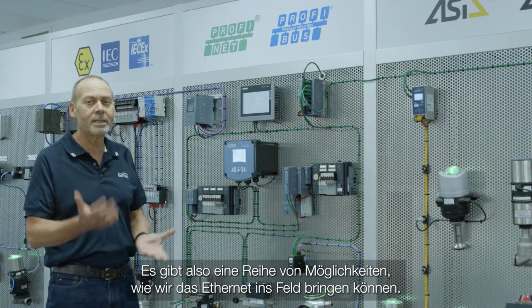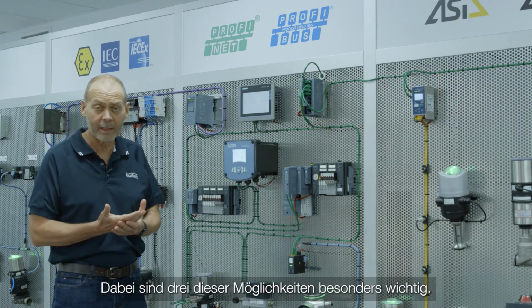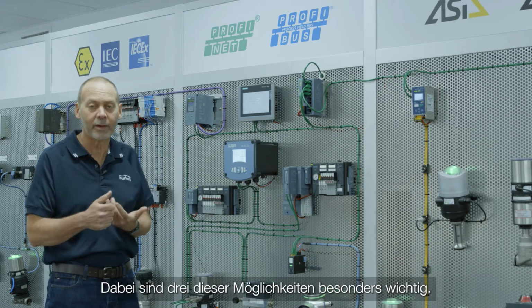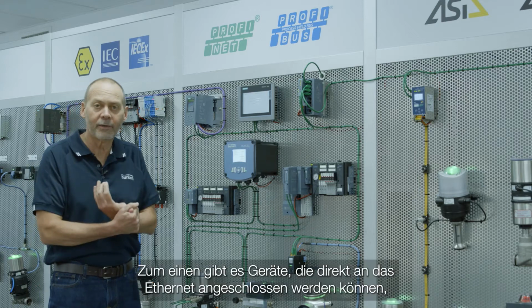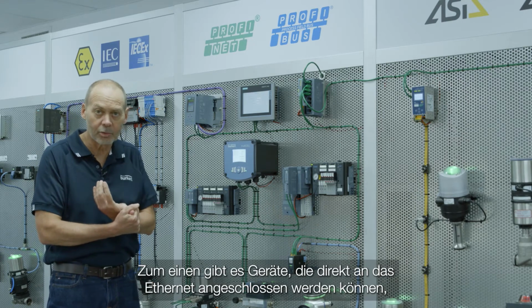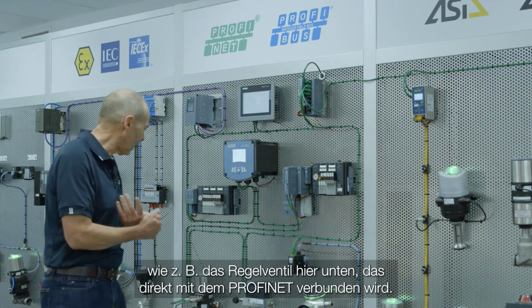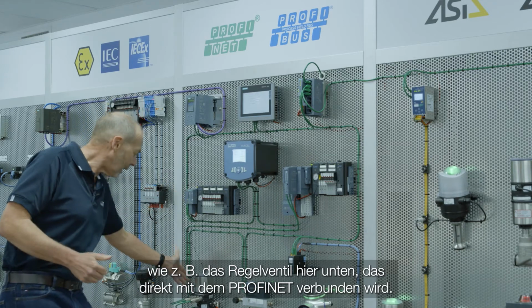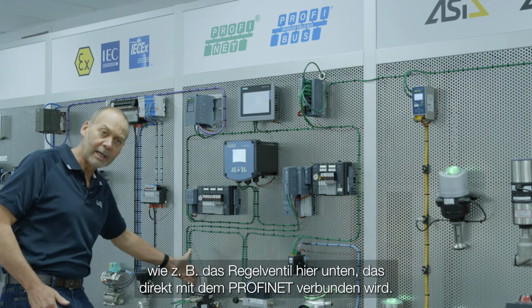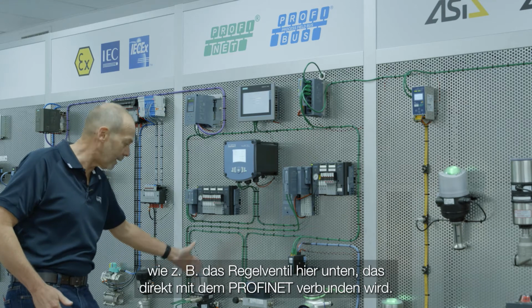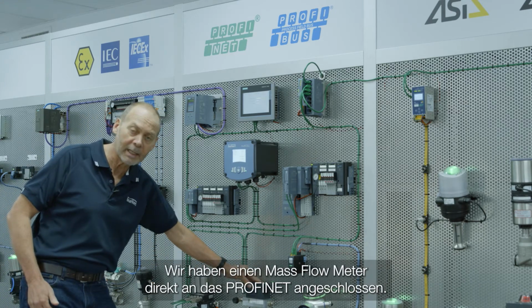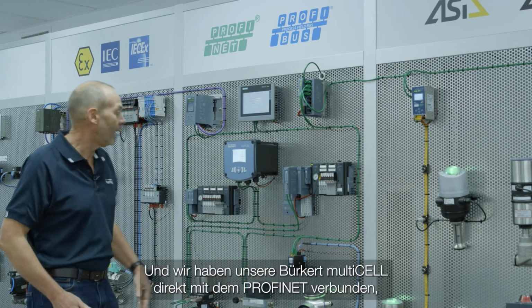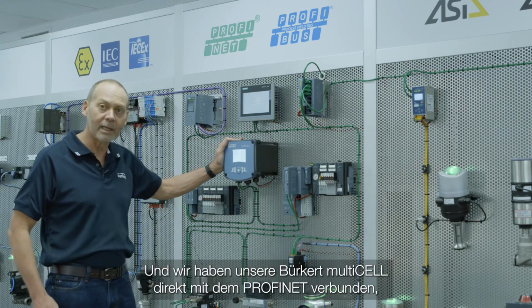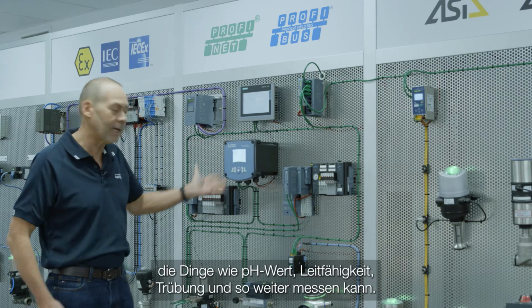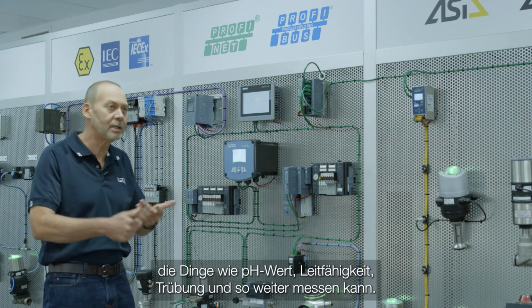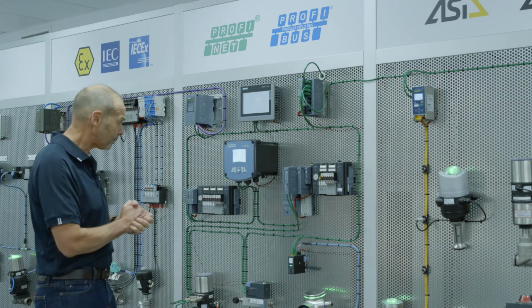So there are a number of ways that we can take Ethernet to the field, and there's three main ways you really have to consider. One is having devices that connect directly to Ethernet. As an example here, we've got a modulating control valve connected directly to the PROFINET. We've got a mass flow meter connected directly to the PROFINET, and we've got our Bürkert multi-cell connected directly to PROFINET, which may be taking in things like pH, conductivity, turbidity, etc.